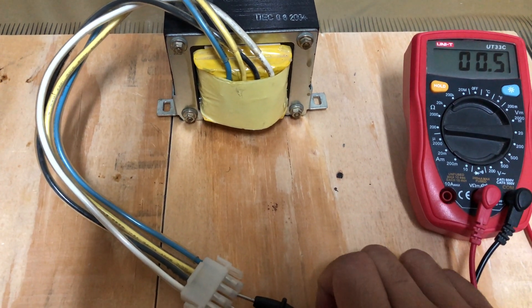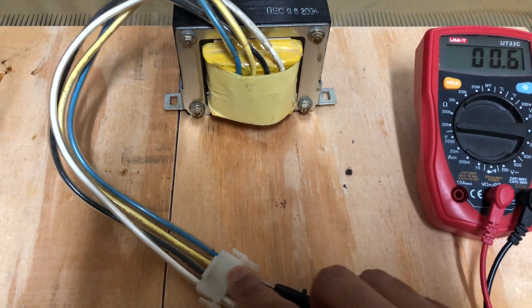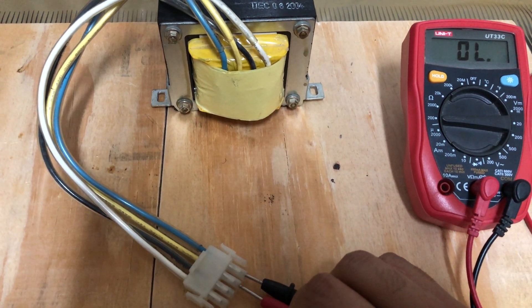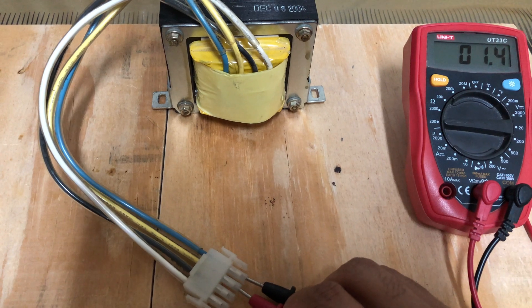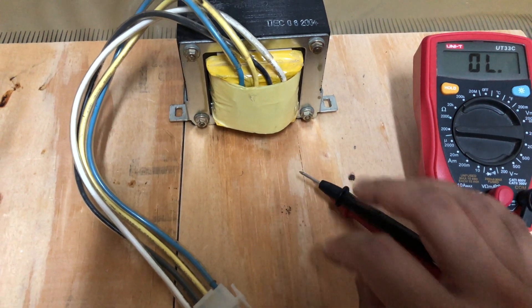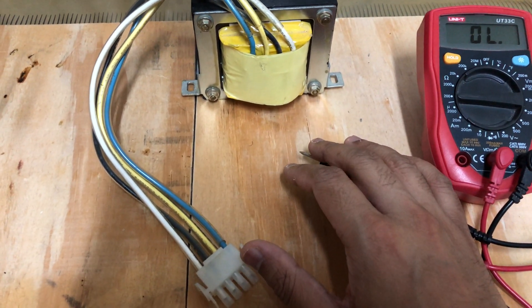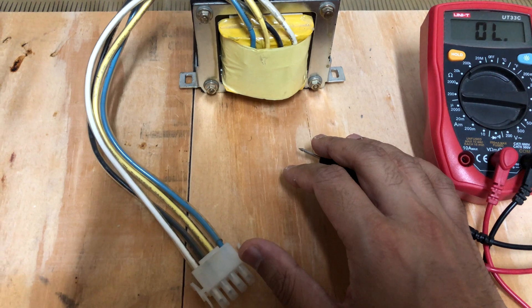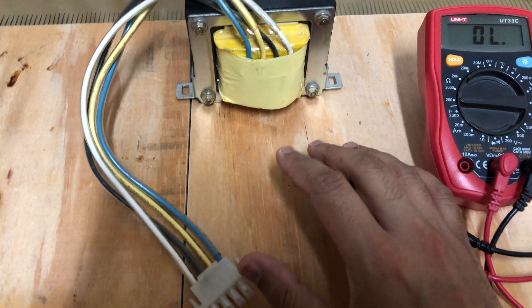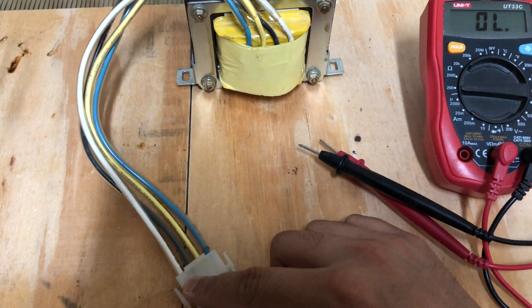Let's probe between these two connections and see — this is only 0.5 ohms. What about this one? Also 1.4 ohms. So as you can see, it looks like these are taps from the same winding.